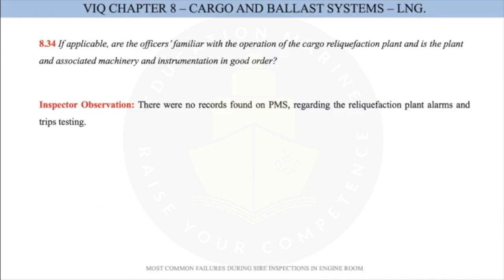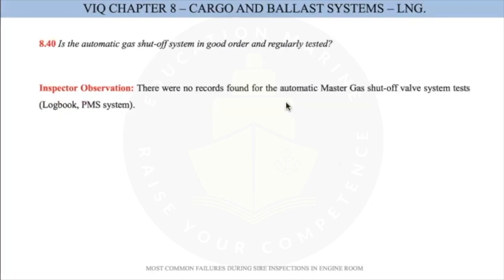That is also a big observation. As we discussed before, you need to check your manual for the scheduled maintenance, and if as per the book there are some trip checks, you need to perform them and record them in the planned maintenance system or make a statement in the logbook. Is the automatic gas shutoff system in good order and regularly tested? Inspector observation: there were no records found for the automatic master gas shutoff valve system tests, in the logbook or planned maintenance system.